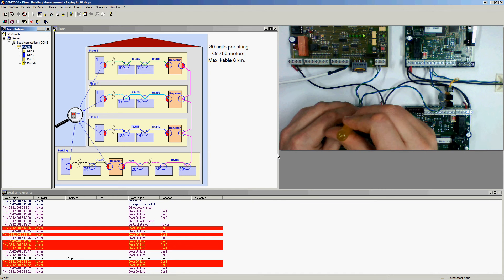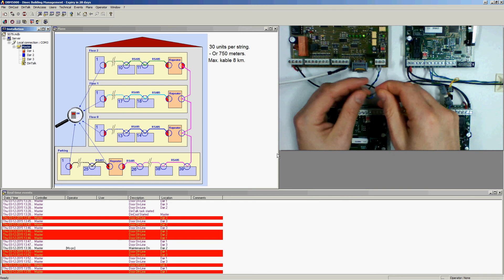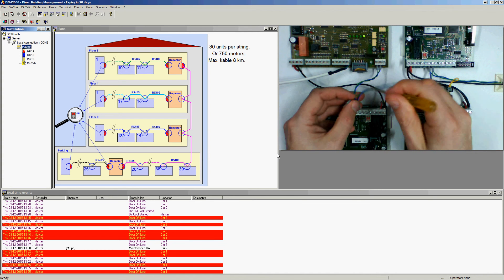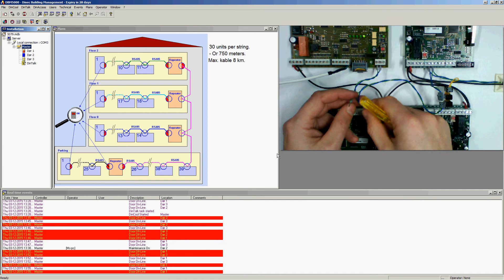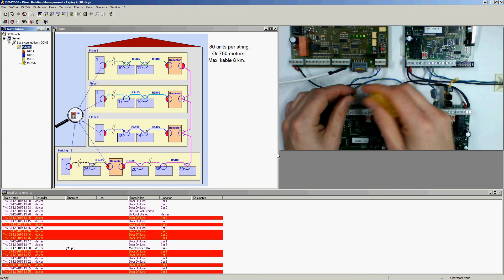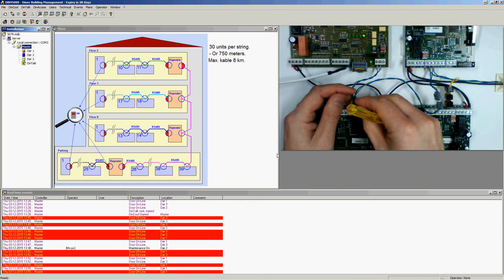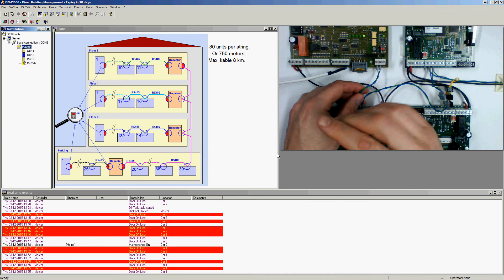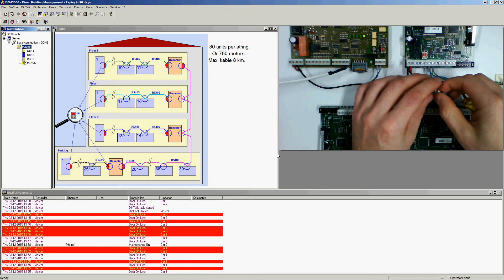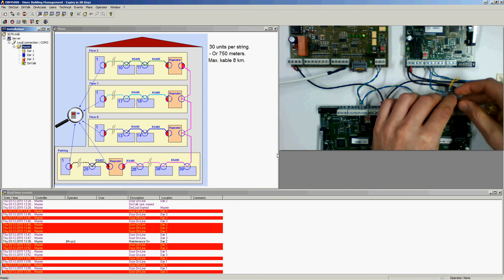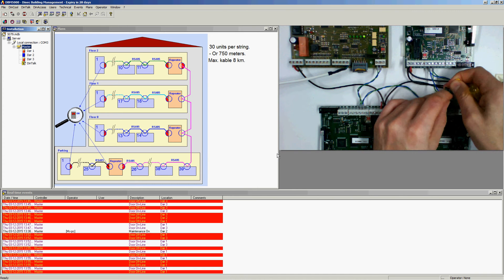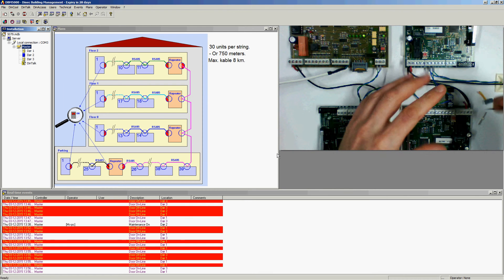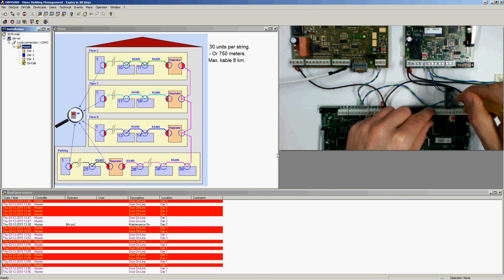A good idea when you do the bus installation is, as a minimum, to connect the earth or the bus installation like this — where you have them connected — because in that case your twisting of the cable would be as it should be from the start. You can also isolate these two and have the installation going through the wires to the next door, which gives a good connection. And if you can — I know it will cost a little extra — then the small PCB we have to the right is really a good thing when you have to make a test or find damage on the bus. As you can see, it makes it easy to just test whether the units or doors are working, and if I have a door nearby I can also just leave that to the third connector we have here.